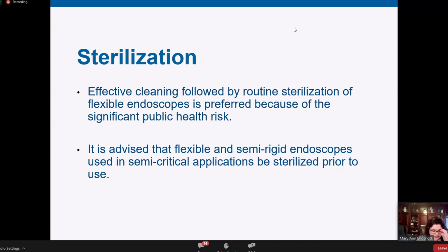So what I recommend for sterilization is looking at the models of scopes that you have. You should already have an inventory of what types of scopes you're using within your facility. But then I need you to dive deeper and take a look at what compatible methods are available or not available, are validated for that type of endoscope. What I mean by that is, in the endoscope IFU and in your instructions or validation from your sterilizer manufacturer, they'll tell you what they've tested and what's validated for what systems. So look at your inventory and see what it's already compatible with.